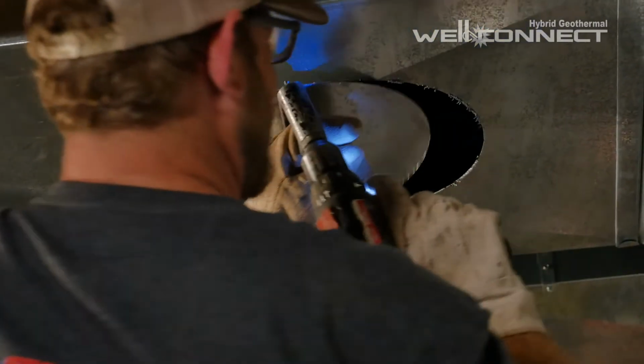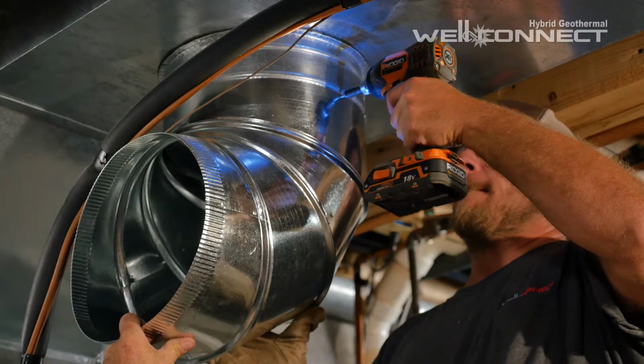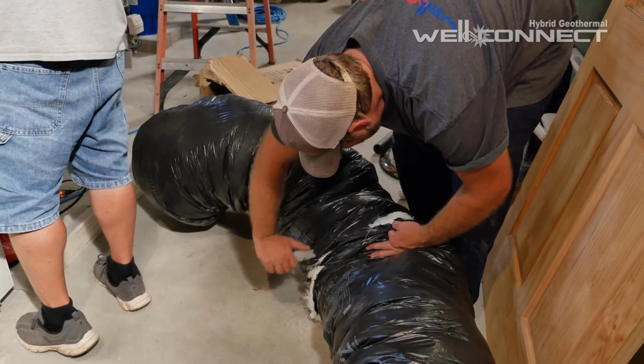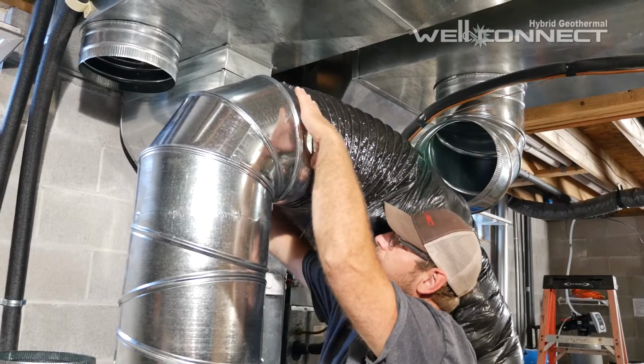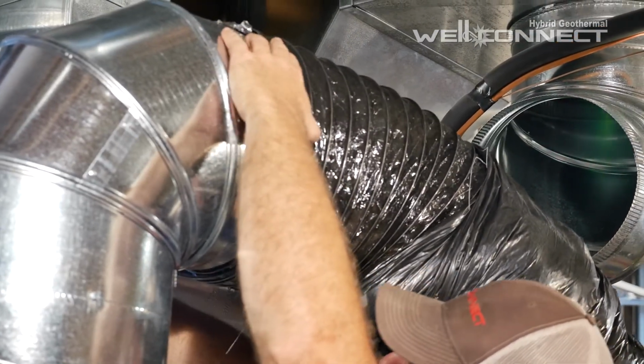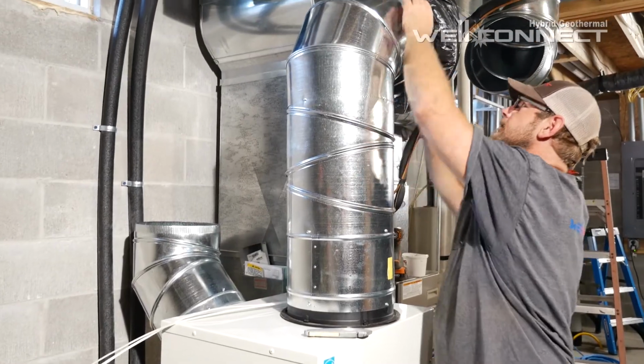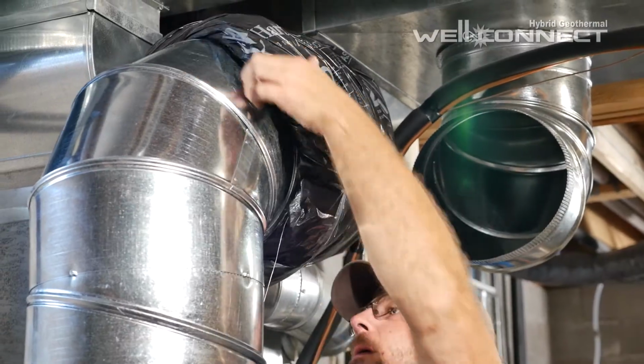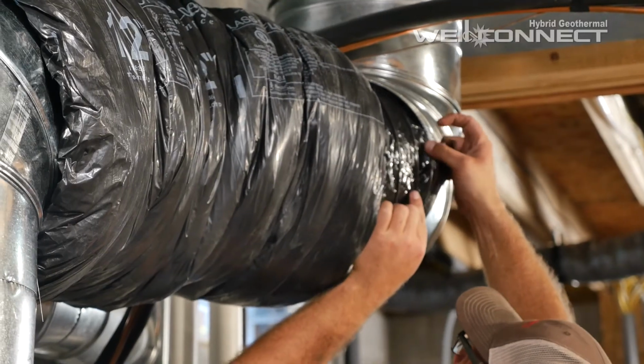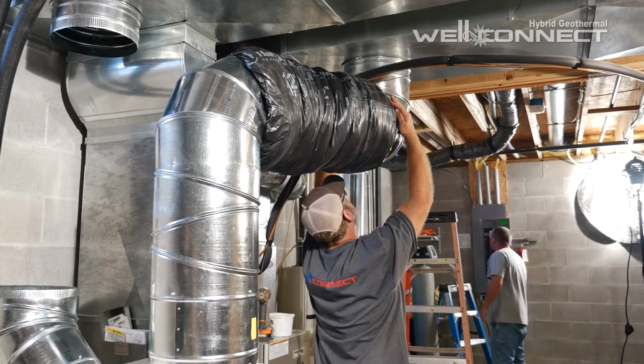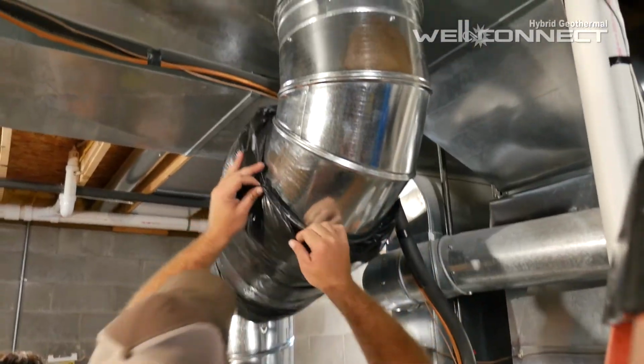Now cut a 12-inch hole in the furnace plenum or supply duct where the Well Connect supply air will be attached and install a 12-inch start collar. This point of connection must be downstream from the backdraft damper. With the Well Connect in its final position, run the necessary 12-inch duct, either flex or metal, from the Well Connect air discharge to the collar on the furnace supply duct.